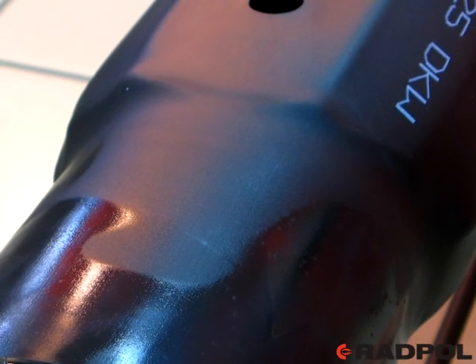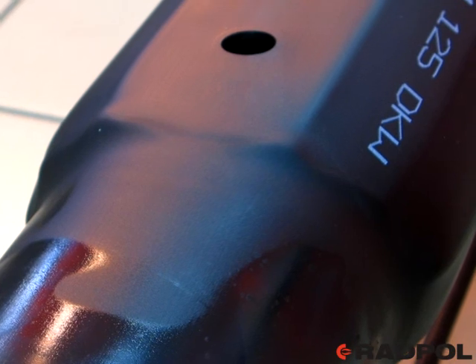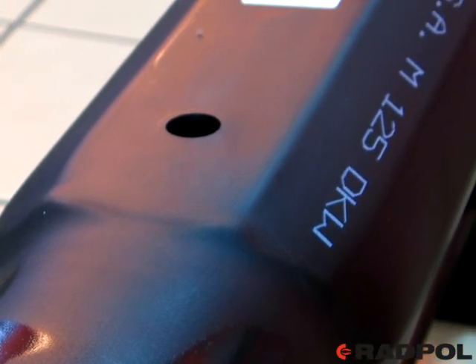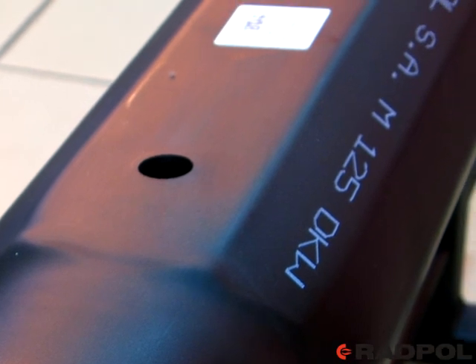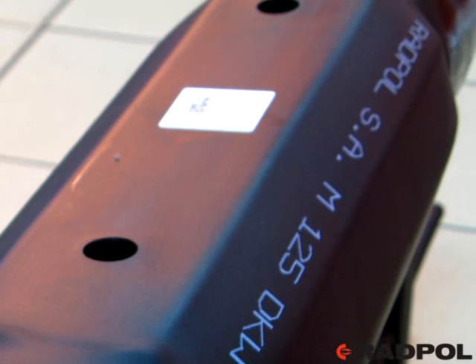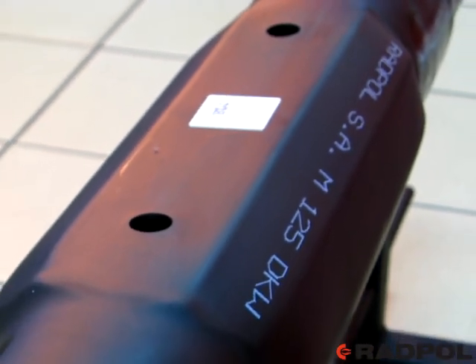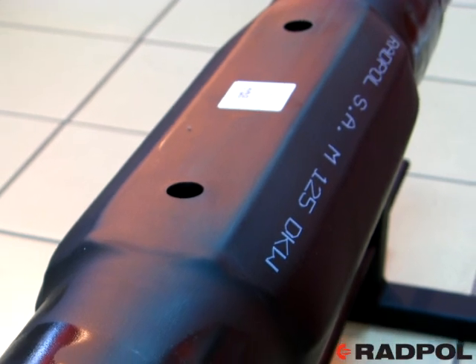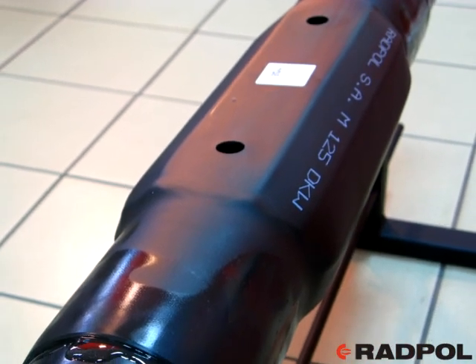Recommendations concerning pre-insulated joints advise performing a tight test of the joint under a pressure of 0.2 bar. The joint is tight if the pressure remains the same for at least two minutes. The test should be carried out once the joint cools down below 40 Celsius degrees. If the installation of the heat shrink joint by Radpol is worked out properly, the tight test is not necessary.